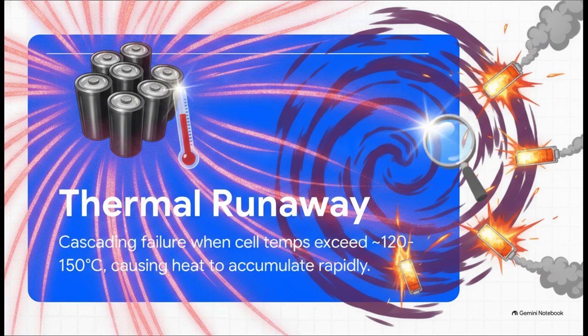If the cooling systems can't dump that heat fast enough, a single failing cell heats up its neighbors in a cascading chain reaction. Once internal temperatures hit 120 to 150 degrees Celsius, the chemical reactions become entirely self-sustaining, and heat builds up faster than it can possibly be removed.